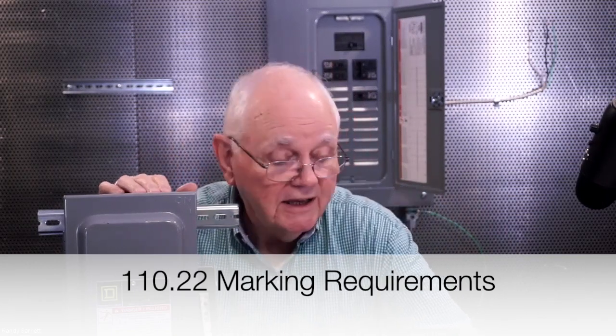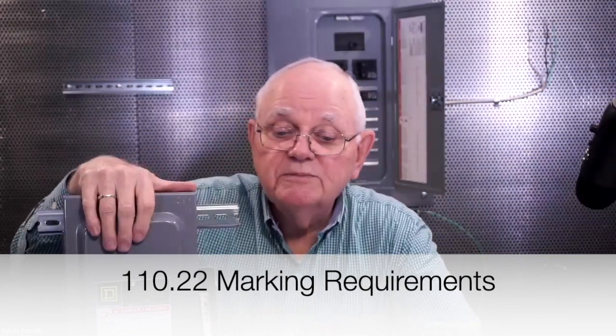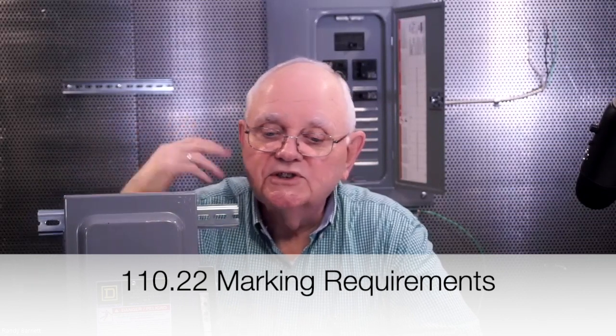110.22 tells me that my disconnect must be marked. And of course, we just use this one for training, so it's not. But my disconnect must be marked. It must be marked legibly and durably. So not with a black Sharpie or anything like that, right? And it's got to be marked as to what its purpose is. You might put CW number 3 up here, chill water pump number 3 or something like that, whatever it supplies.